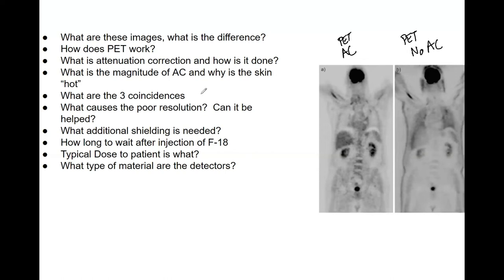What causes the poor resolution and can it be helped? The annihilation between a positron and electron takes place about one millimeter from the positron emission, and that annihilation occurs at 180 degrees plus or minus 0.25 degrees. Because it's not perfectly 180 degrees, this limits resolution to about two millimeters. Since this is a fundamental property of how annihilation works between a positron and electron, it cannot be helped — that is the fundamental limit of PET resolution.